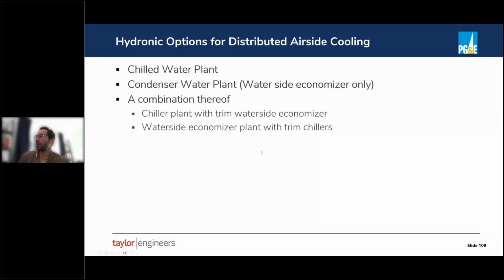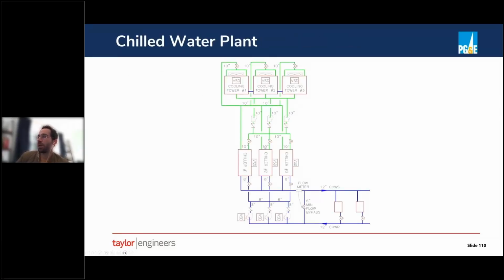So here's an example of a pretty plain vanilla chilled water plant. We haven't yet added the complication of a waterside economizer to this design. What you're seeing is 3 chillers in parallel. We have a primary only distribution configuration, meaning we have a single set of pumps that is sending water through both the chillers as well as out to the distribution system. This is the data center. We can imagine it's a small one that only requires N+1 redundancy. So 2 of these chillers are required for design load. The other one is redundant.